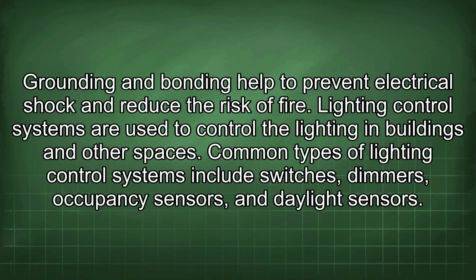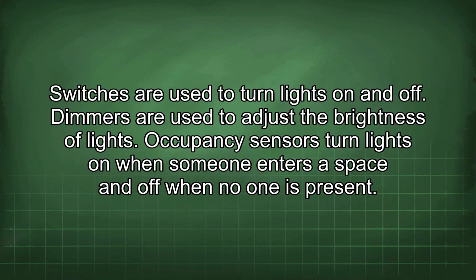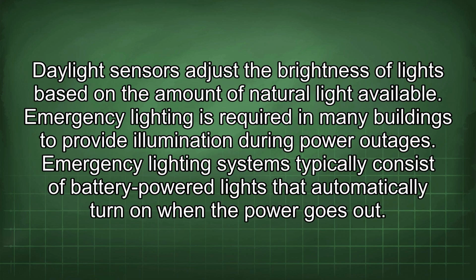Lighting control systems are used to control the lighting in buildings and other spaces. Common types of lighting control systems include switches, dimmers, occupancy sensors, and daylight sensors. Switches are used to turn lights on and off. Dimmers are used to adjust the brightness of lights. Occupancy sensors turn lights on when someone enters a space and off when no one is present. Daylight sensors adjust the brightness of lights based on the amount of natural light available.